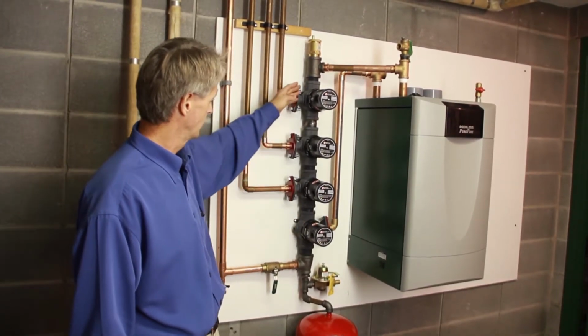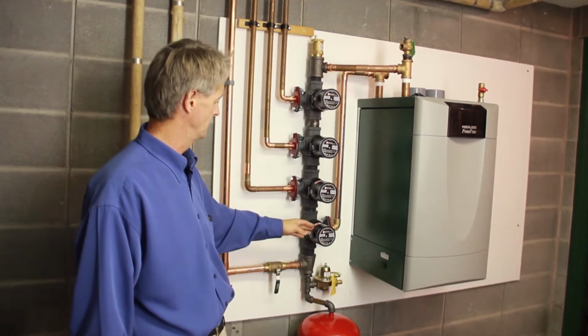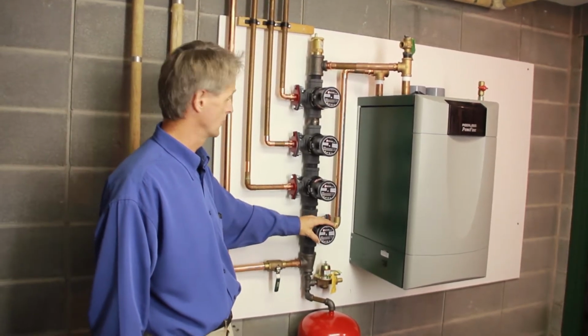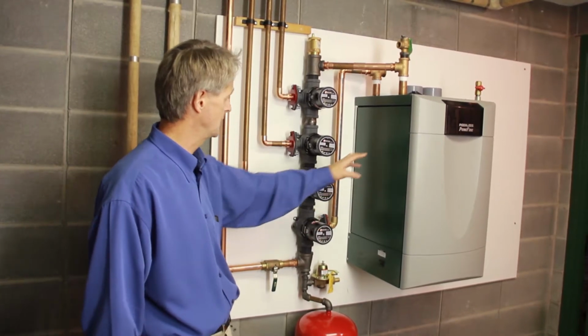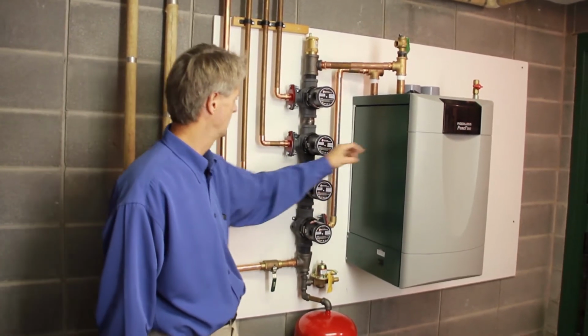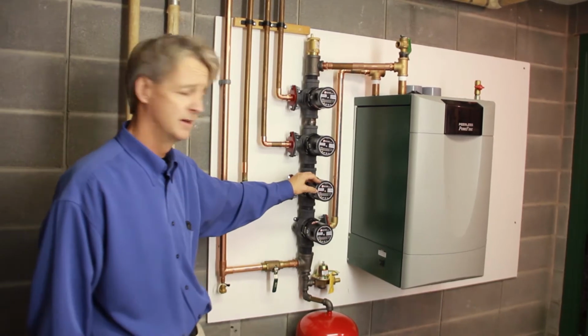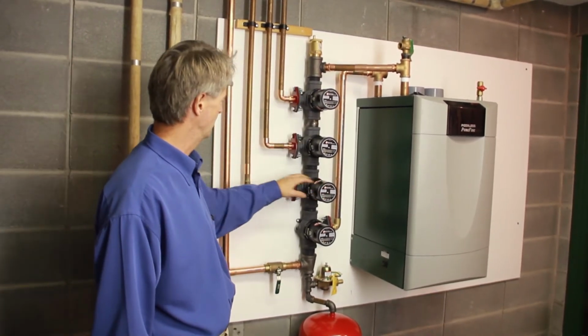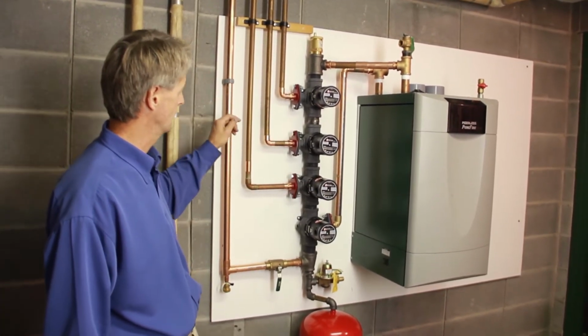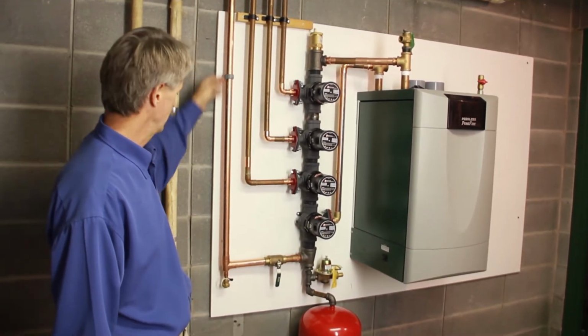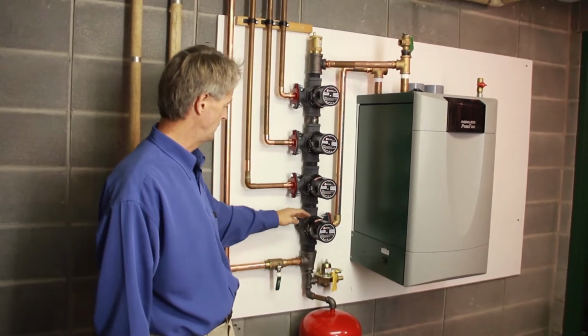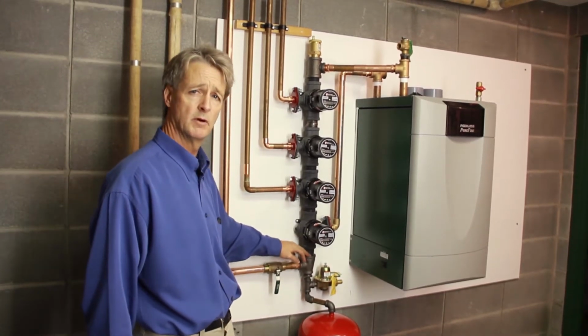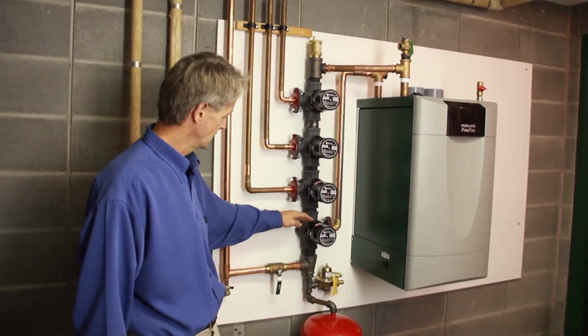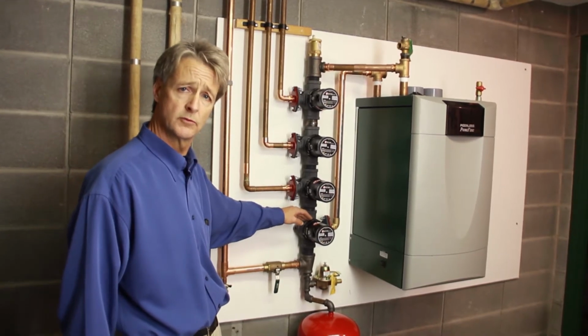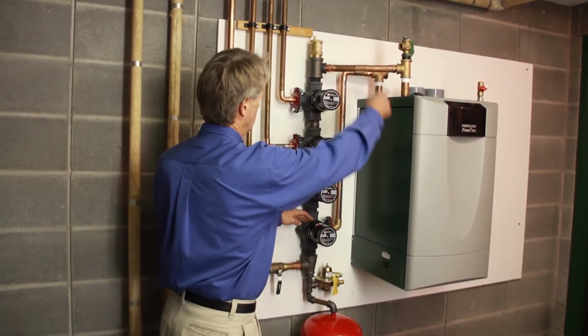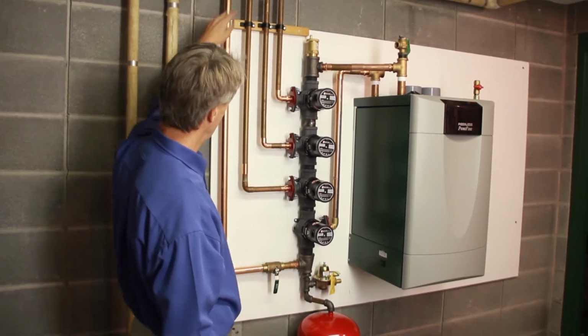The common pipe is the source of water for all four pumps. The lower pump is our dedicated boiler pump and keeps an adequate flow in the heat exchanger of the boiler when it's running, regardless of what the zone pumps are doing. The three zone pumps also draw off the common pipe and discharge their water out to the respective zones. Water returning from the zones is able to enter the common pipe through the fitting we've added on the bottom of the common pipe. This completes the two circuits: our primary boiler circuit and our secondary zone circuit.